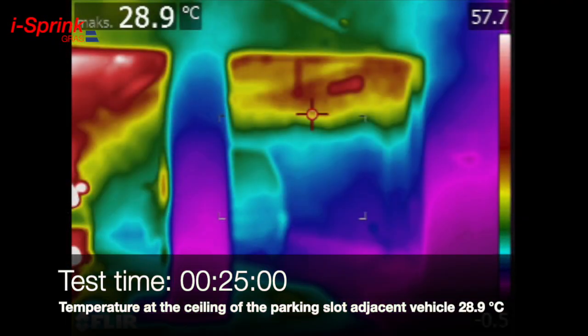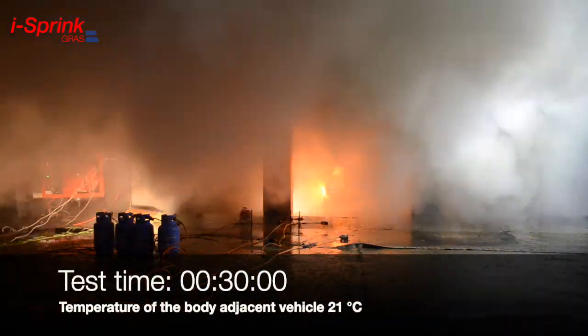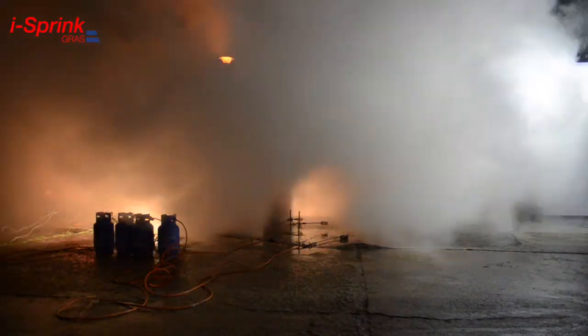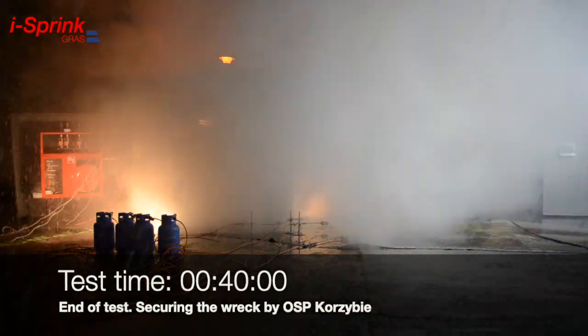The temperature at the ceiling above the neighboring vehicle is only 28.9 degrees, and the body temperature of the neighboring vehicle is 21 degrees. The lack of new flames and the reduction of smoke are clearly visible. The fire was successfully controlled by the i-Sprink system. After 40 minutes, the test is completed and the wreck is secured by the firefighters from the OSP Korzybie unit.